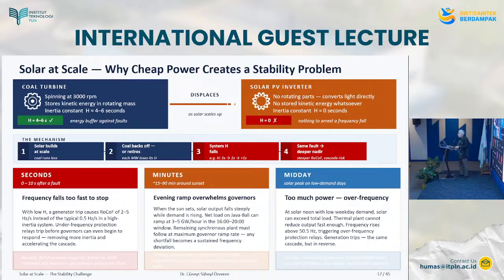But of course, you are not going to shut down the input. What it means is that for 4 to 6 seconds, it can absorb a loss of generation energy. If another generator comes down, it can replace its energy with kinetic energy for 4 to 6 seconds, okay? So it's an energy buffer against faults, and this doesn't need any automatic regulation. It just happens in the system.